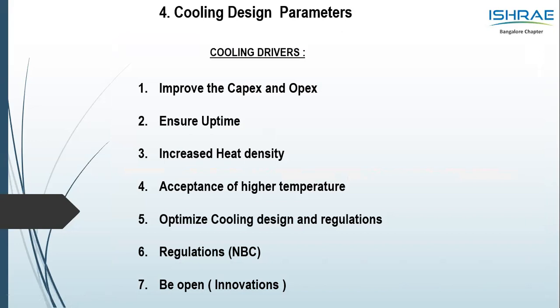So what are the parameters that we will have to keep in mind while we design the right cooling unit in a server room or a hyperscale? Point number one, very important, CapEx and OpEx, you'll have to look at that. Ensuring uptime, we saw it in Tier 1, Tier 2, Tier 3, Tier 4, ensuring uptime, no downtime of the cooling unit. Increased heat density, very important. Per rack, 5 years, 10 years back, 2 kilowatt to 5 kilowatt. Today, as we talk, 10, 15, 20 kilowatt per rack.